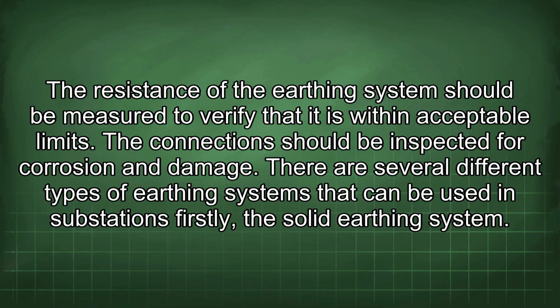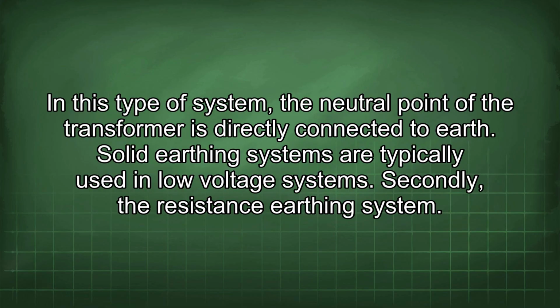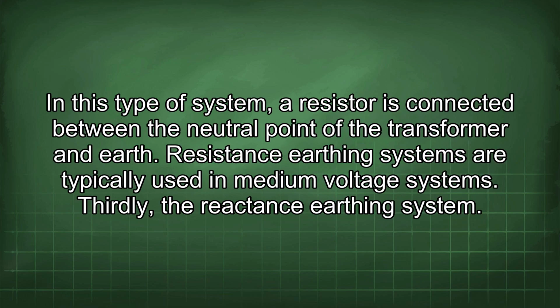There are several different types of earthing systems that can be used in substations. Firstly, the solid earthing system. In this type of system, the neutral point of the transformer is directly connected to earth. Solid earthing systems are typically used in low-voltage systems. Secondly, the resistance earthing system. In this type of system, a resistor is connected between the neutral point of the transformer and earth. Resistance earthing systems are typically used in medium-voltage systems.